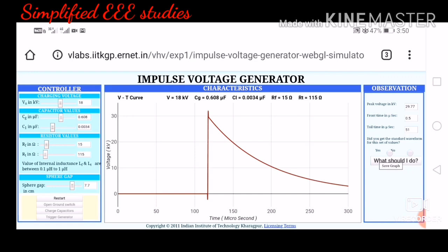You are able to get the waveform — this represents the output of the impulse voltage generator. This is the impulse waveform; during lightning and thundering, these kinds of waves are generated. In the impulse voltage generator, capacitors are charged in parallel and discharged in series. Check the observations: peak voltage is 29.77 kV, wave front time is 0.5 microseconds, and wave tail time is 51 microseconds.